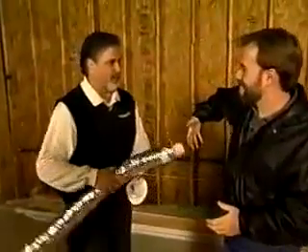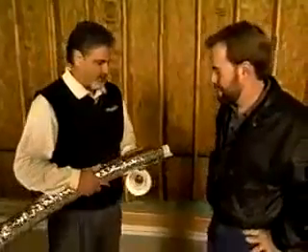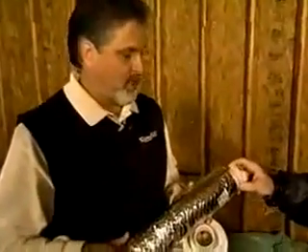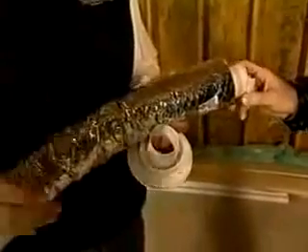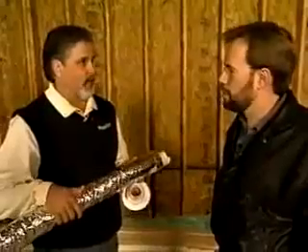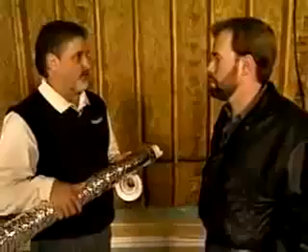Normally when you carry a piece of ductwork it's large, but Unico has something different. It's a two inch diameter tube, three and a half on the outside. Unico is a mini-duct high velocity pressurized system, which means we're pressurizing the duct and velocities are higher, so you're pushing more air through a smaller duct. This generates more aspiration into the room to give the room more even air temperature. The system also removes 30% more humidity than a conventional system, which allows us to dry the air out and have a higher thermostat setting, saving energy.